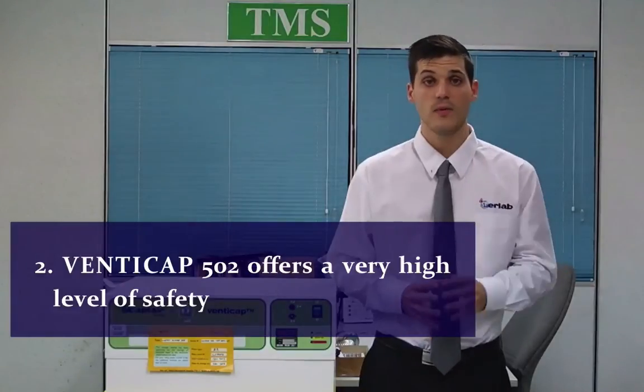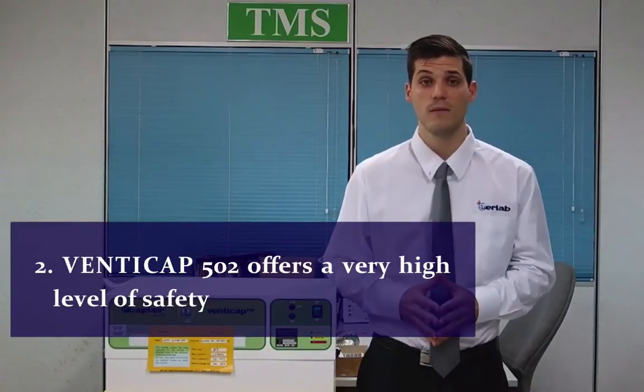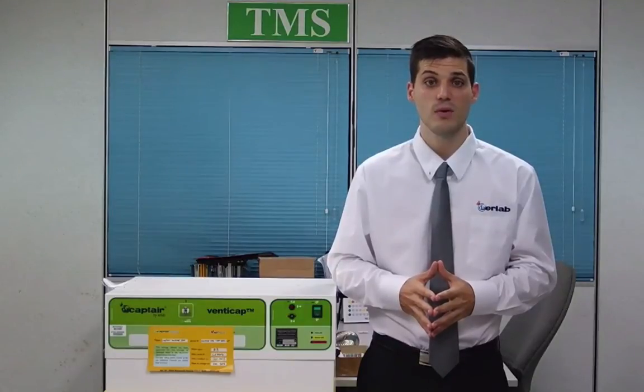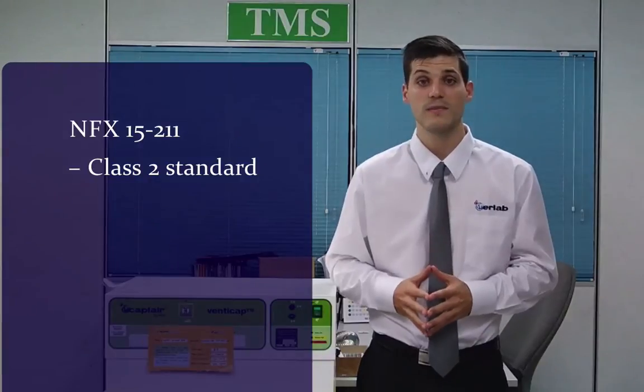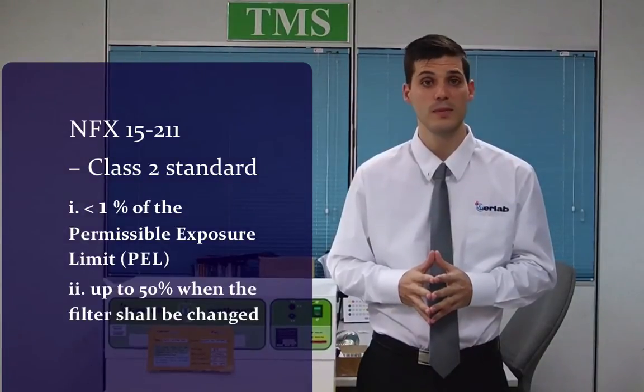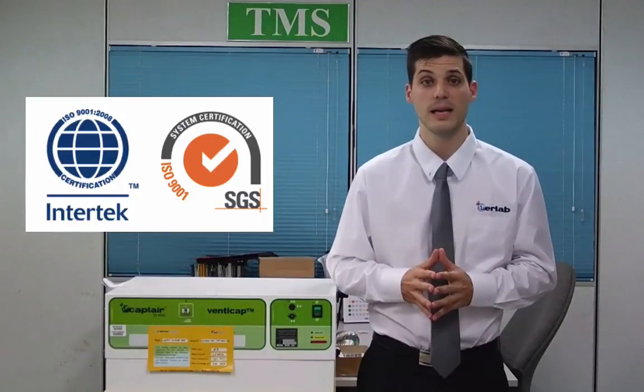Secondly, it offers a very high level of safety. Developed by Erlab, the world's specialist in the filtration of chemicals for the protection of lab personnel since 1968, the VentiCAP 502 offers full protection with a filtration efficiency in full compliance with standard NFX 15211 class 2, which requires that no more than 1% of the permissible exposure limit of a chemical should be recirculated into the room — up to 50% saturation when the filter should be changed. Erlab filtration systems have been tested by independent laboratories such as Intertek and SGS.